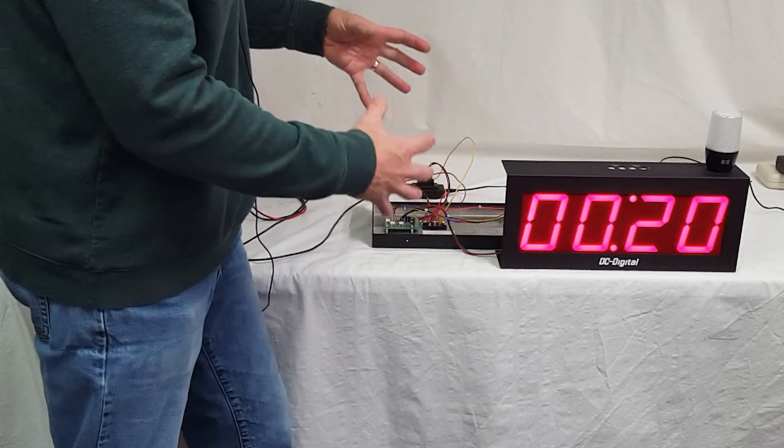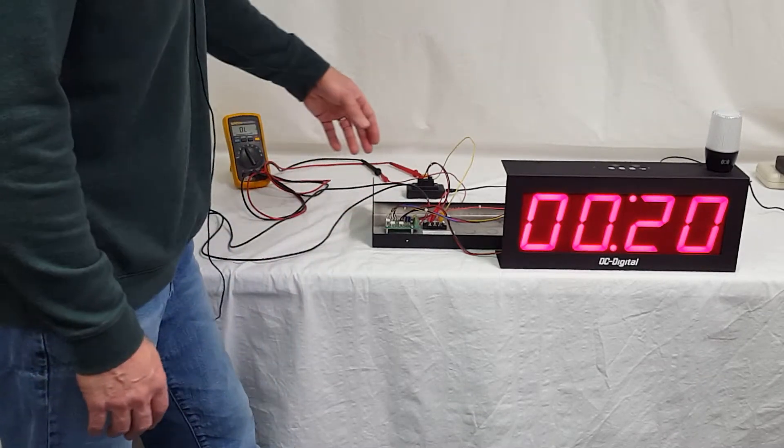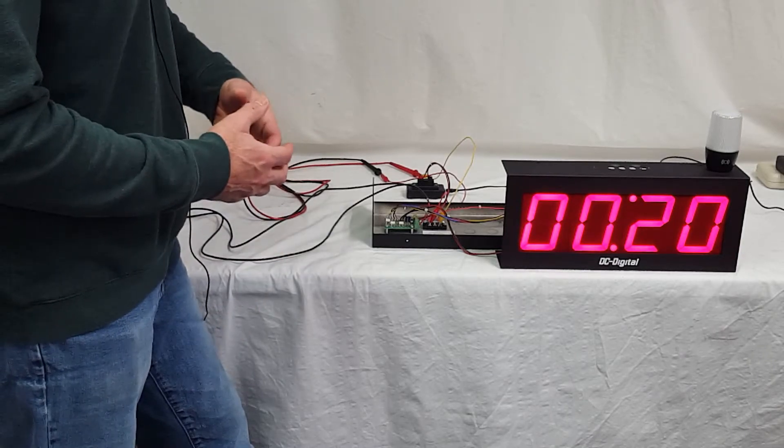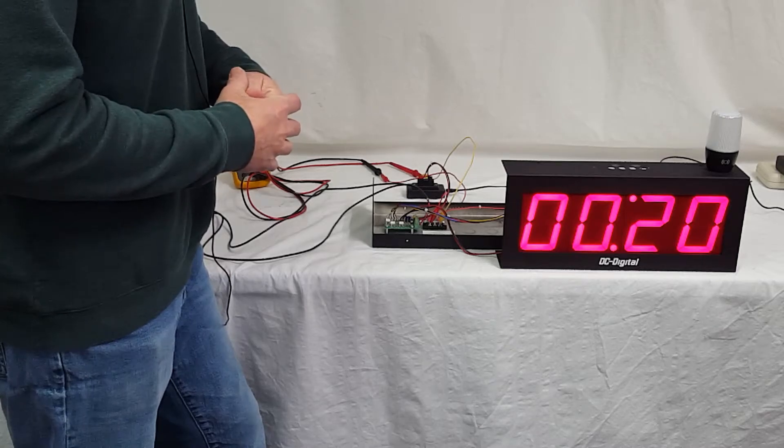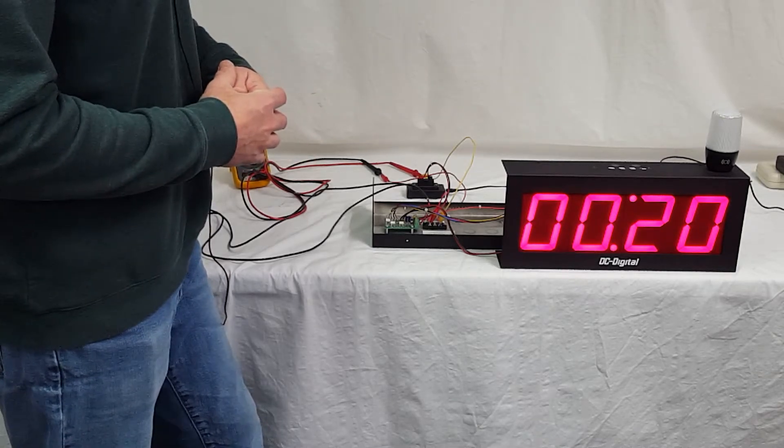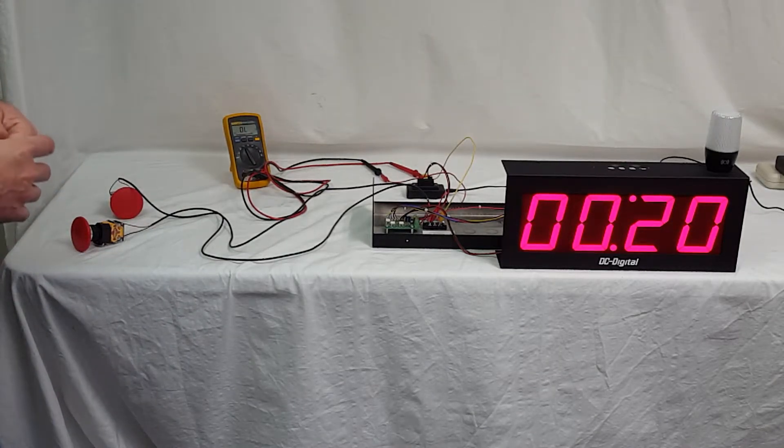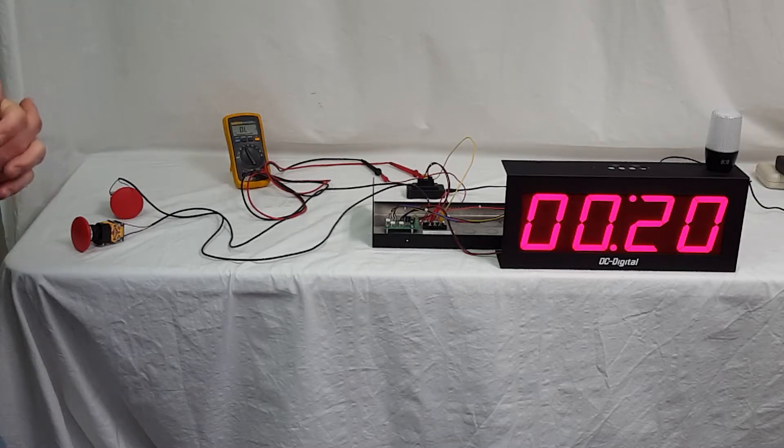I've got the case split so you can see what's going on in the background. I've got a Fluke meter on continuity to give you the audible indication of what's going on with the relay. And I've set up a couple of switches here to simulate what the customer is going to be doing with the countdown timer.